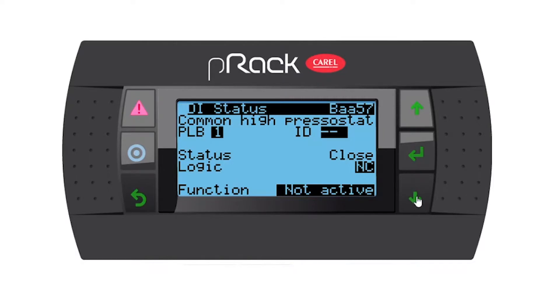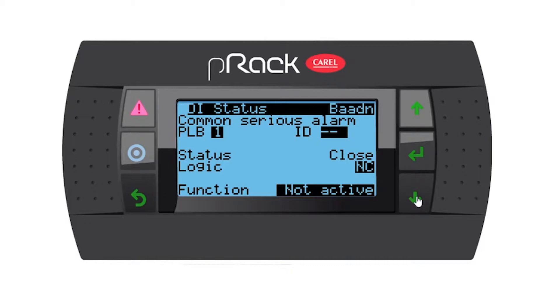Common high pressure stat — I don't have one, so I don't assign it. Going down, compressor inverter warning — if you have it, assign it; I'm not going to. Common serious alarm — if you have one you have the option to assign it. Alarm one compressor one — yes I do have one, so I'm going to enter, assign it to number two, leave the logic as normally closed. I'll do the same for compressor two and compressor three.